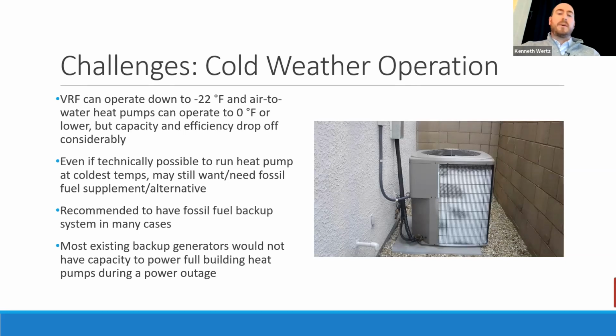Next one, a lot of people are conscious of this already. There's been a stigma over the years that heat pumps can't operate at cold temperatures, especially in this part of the country. It used to be that for VRF systems or other types of units, once you got below 32 degrees outside, you had to shut them off because they couldn't generate heat anymore. And the technology has improved pretty significantly in the past 10 to 15 years. Most VRF systems, the condensers can operate down to minus 22 degrees outside. And they maintain full output, full capacity down to minus 13, which is great. It's a lot better than it used to be. And that covers 99.9% of the hours of the year in this area. But it doesn't cover every single hour.